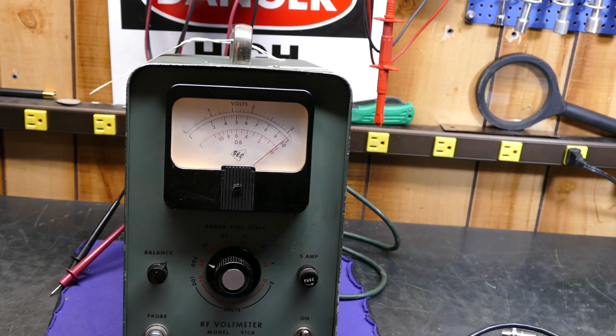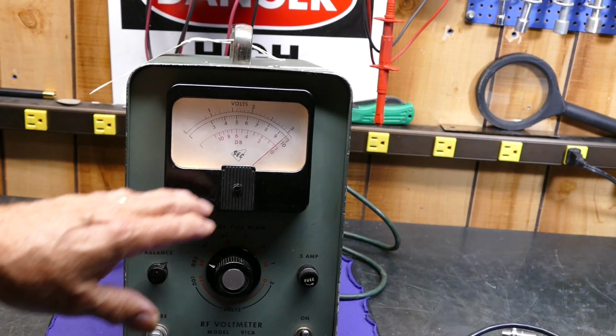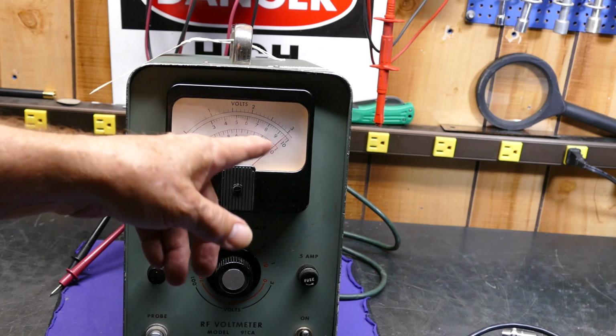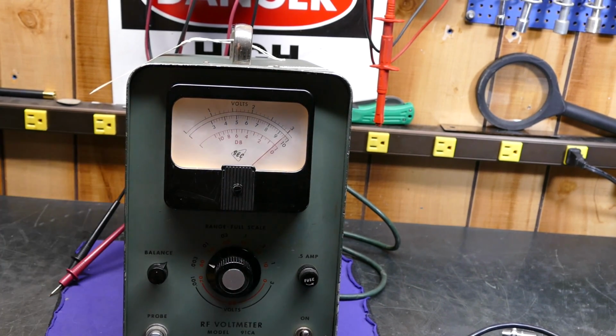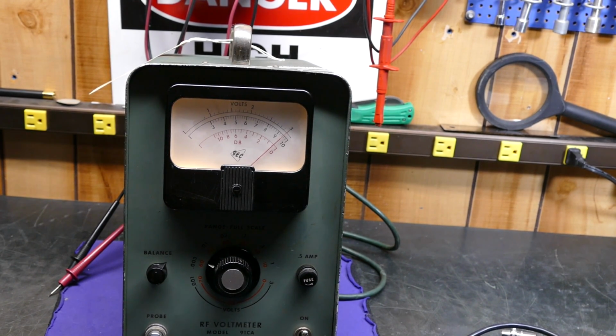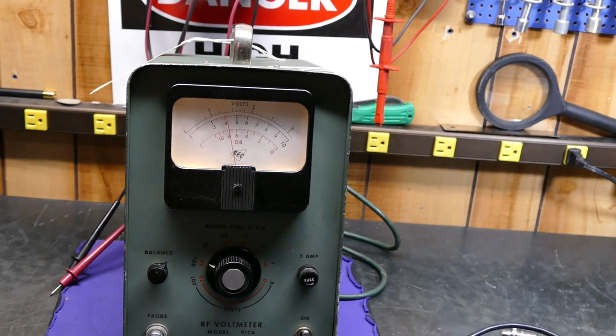It takes it a second, and the manual tells you this. If you overload it, it takes it a second to settle down. There it is. It's coming back, and if you look straight on, there's 3 millivolts. We'll go to 1 millivolt. 1 millivolt. So this thing is sensitive.